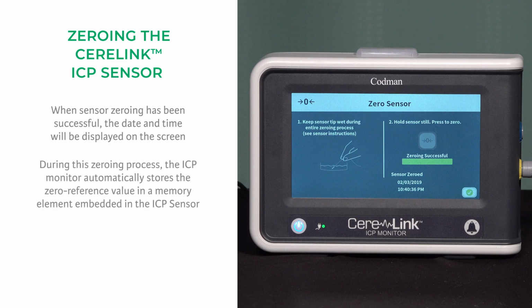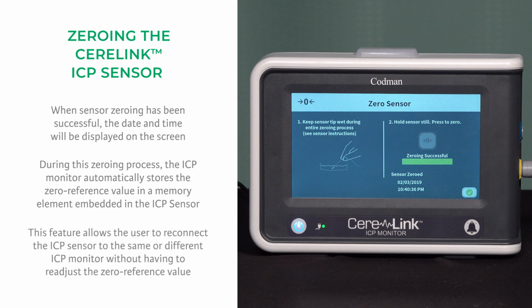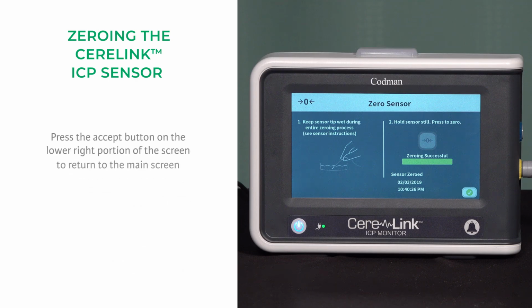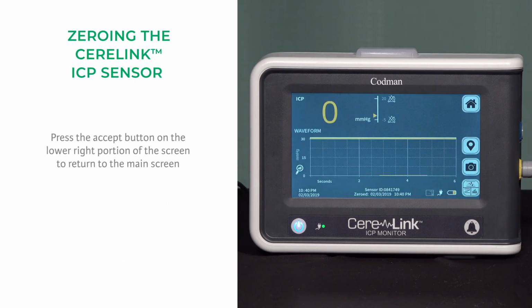During this zeroing process, the ICP monitor automatically stores the zero reference value in a memory element embedded in the ICP sensor. This feature allows the user to reconnect the ICP sensor to the same or different ICP monitor without having to readjust the zero reference value. Press the Accept button on the lower right portion of the screen to return to the main screen. Now the ICP sensor is ready for implantation.